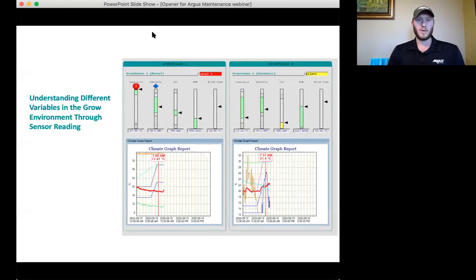So when you think about your preventative maintenance, some of the things that you really want to take a look at are your alarms and then your trends. This is an example of a couple of greenhouse environments, the different parameters that you're looking to hit. So we have temperature, humidity, CO2, and so forth. And one of those, the temperature one, is in a level 3 alarm. So you want to figure out what that level 3 alarm is, and most importantly, how frequently it seems to happen, because that may give you an indication that some pieces of equipment are not doing so well.